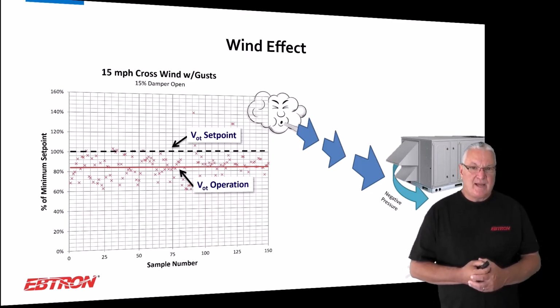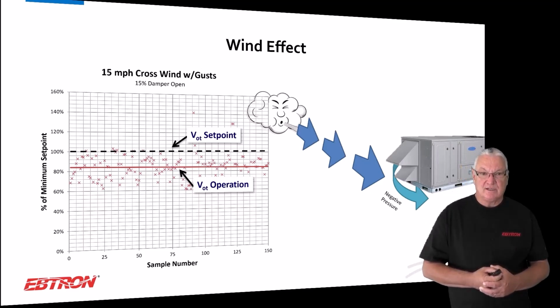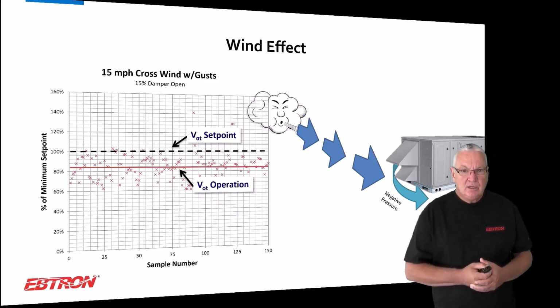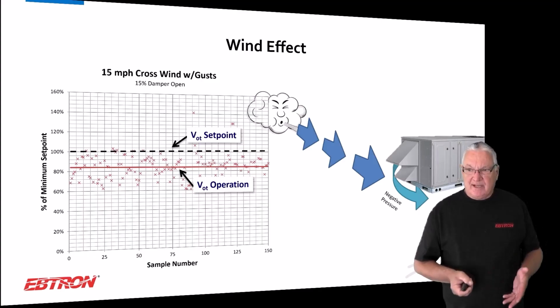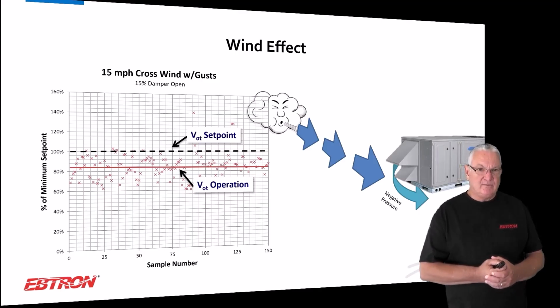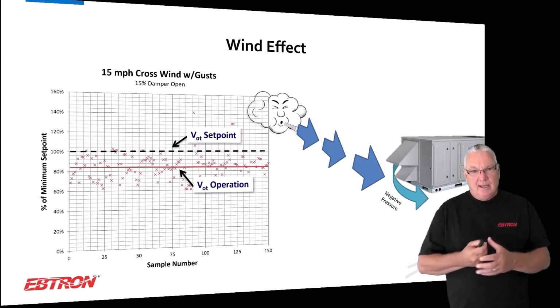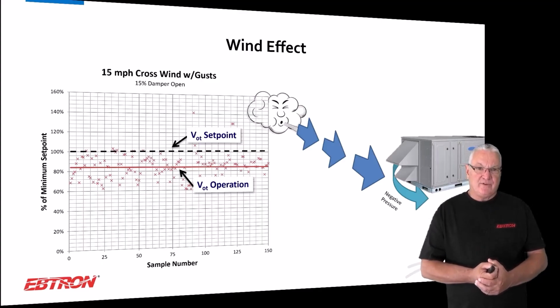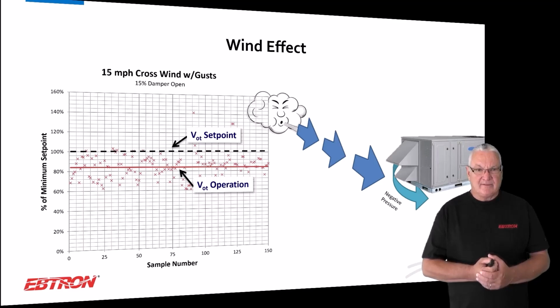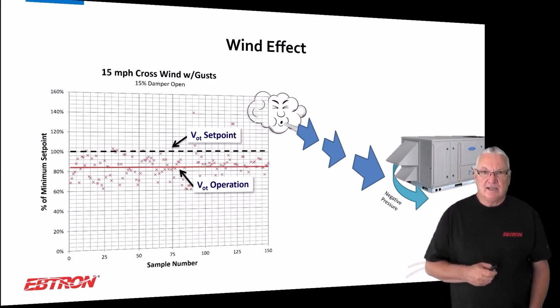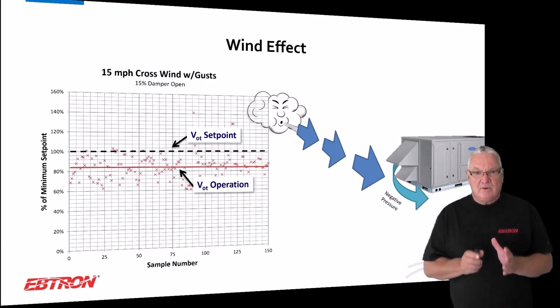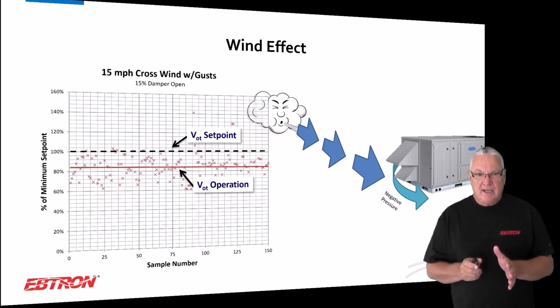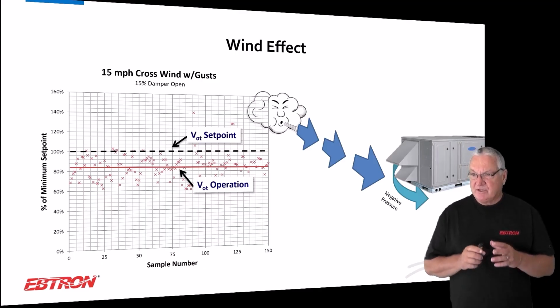And then this is from actually our building. We monitor and look at wind speed and things like that. And really, one day we set the building up on a calm day, no significant wind, and we set it up for that black dash line at 100%. And we came back on another day where we measured a nominal 15 mile an hour wind down the side of the building. So it was a negative pressure on that intake, and if you looked at the average flow, it was almost a 20% reduction. And the reason we put the scatter on it, the scatter is the actual data that we took, and the reason we do that is we try to explain to people, it's like wind going down the side of a building isn't a constant speed, and it's not a constant direction, so it's moving quite a bit, in magnitude and direction.